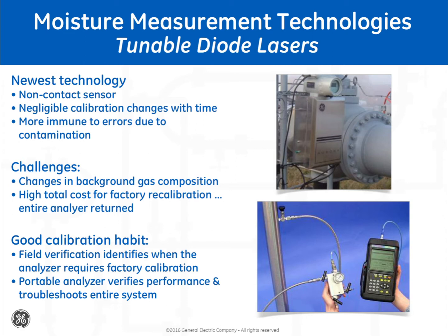If the readings do not exactly agree, and if the operator feels that the portable is providing the expected reading, some analyzers offer a 1-point offset. If the readings differ by more than the combined error budget, this is where further investigation is required. Whether using a portable or if the analyzer has an integral verification system, a regular verification program provides peace of mind that the analyzer is operating and is able to respond to changes in moisture.